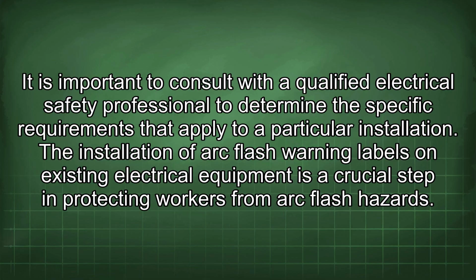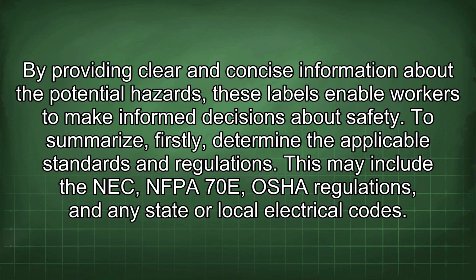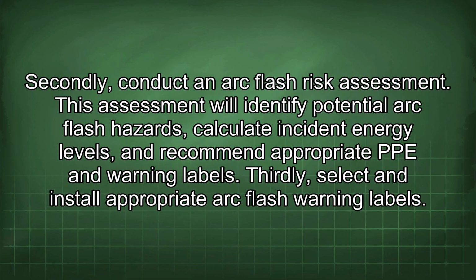The installation of arc flash warning labels on existing electrical equipment is a crucial step in protecting workers from arc flash hazards. By providing clear and concise information about the potential hazards, these labels enable workers to make informed decisions about safety. To summarize, firstly, determine the applicable standards and regulations. This may include the NEC, NFPA 70E, OSHA regulations, and any state or local electrical codes. Secondly, conduct an arc flash risk assessment. This assessment will identify potential arc flash hazards, calculate incident energy levels, and recommend appropriate PPE and warning labels.